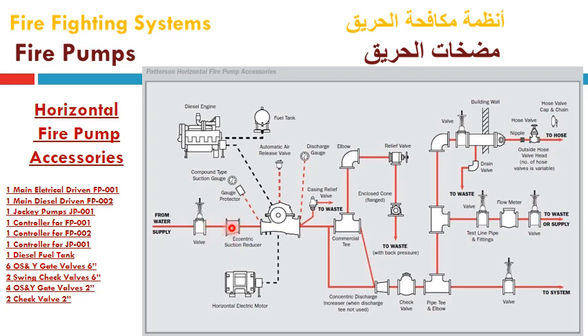used on the suction side to adapt the suction line diameter to the suction flange of the pump, and the isolation or OS&Y gate valve should be provided here on the suction line to isolate the pump from its water supply, which may be an underground tank, overhead tank, or city main supply. Then on the discharge line we can use a commercial T from any pipe fitting provider, and elbows which will be connected to the relief valve to the waste cone using this enclosed cone flanged to the waste, and the main discharge line will go through this side.